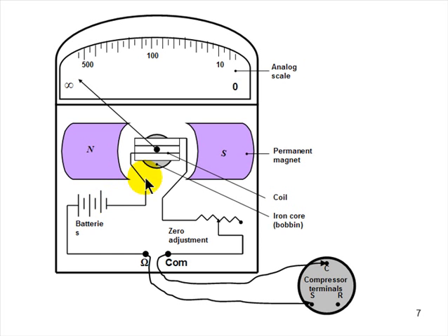So if I send 4 volts out into this circuit out here, and 4.5 volts come back, that's going to go hard to the right because I have my most power and I can overcome that resistance. Now, if I send 4.5 volts out and no volts come back, the needle doesn't move because I can't create a magnetic field in here. And this is where your zero adjust comes in. Basically, what your zero adjustment is doing is correcting for how weak these batteries have become over time. You will find that eventually you zero this out as far as the dial will allow you to, and it's still not zero. That simply means it's time to change your batteries.